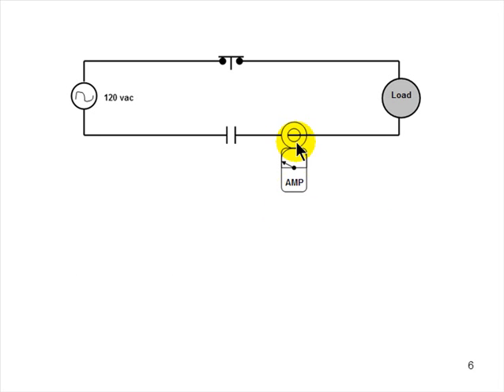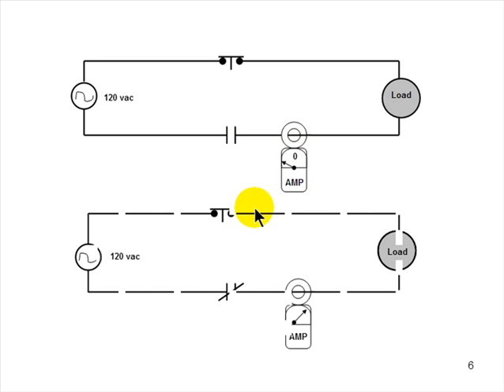Ammeter, of course, if the switch is open, you're not going to have any reading. This thing doesn't feel the intensity of the magnetic field until current is flowing. And if the switch is open, no current is flowing, you're not going to see any amp draw. In this case, it's closed, and of course you're going to read whatever the value is, 9 amps if that's a 9 amp motor, whatever. Pitting doesn't have anything to do with anything. It will simply cause a different amp draw here, which will be different than what it should be, that's all.